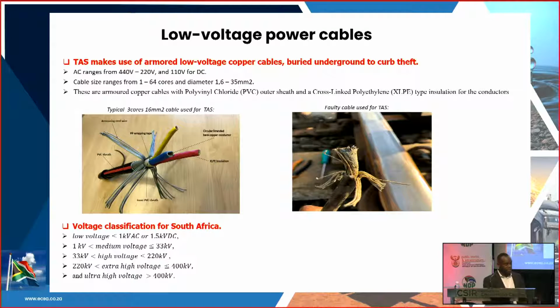A typical new cable, shown in the picture on your left, is a 3-core cable that we use for TAS. This very same cable type - this one was found somewhere in Mpumalanga where a cable had failed. We dug it out and found it in that condition. On close inspection, we found that all the inner cores of the cable were flooded with water.